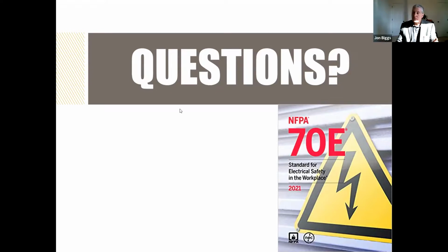He says they have machine-specific lockout tagout diagrams and procedures posted on each item, so that would be what they're looking for. But they also want to see that in your electrical safety program, you address this condition policy so it mentions to employees that if you get a new piece of equipment in, like a large air handler or a very complex system, they're responsible for developing equipment-specific written lockout tagout procedures to put it in an electrically safe work condition.